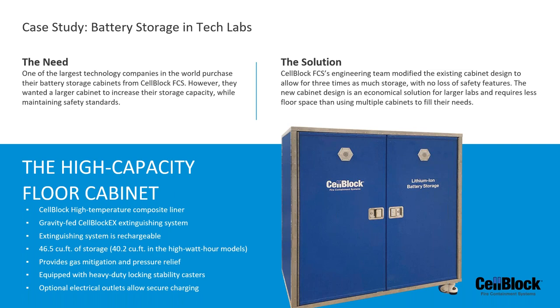One thing that's very important is pressure mitigation, right? If you're going to have an incident in these cabinets, we can't turn the cabinet into a bomb. So we're controlling the air. We know exactly what the energy containment rating is for that cabinet, and we give the rating. The cabinet we're looking at right there has an energy containment rating of 30 kilowatt hours. So based on the rating for that particular unit, we know how many pressure relief valves to put in.